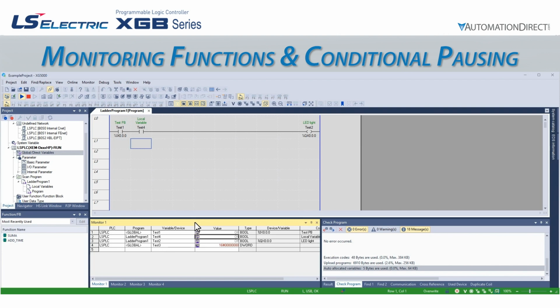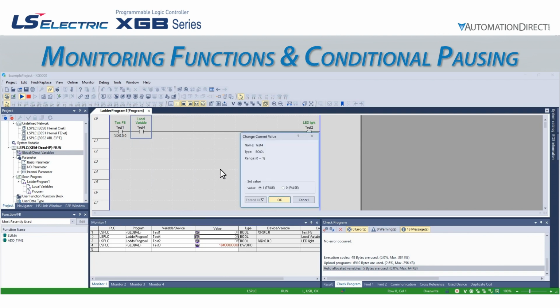We have two ways of editing variables while in monitoring mode. We can edit the variable from the monitor window, or we can edit it directly from the logic. If we want to edit it from the logic, we can double-click on the variable in the logic. This works for any of the XGB IEC programming languages. It will bring up the Change Current Value screen, which allows us to alter the current value. A Boolean variable will have a true-false option, while other variables may have slightly different data entry options depending on the variable type.